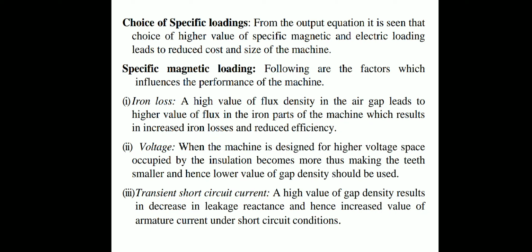Following are the factors which influence the performance of the machine. First point is iron loss. A high value of flux density in the air gap leads to a higher value of flux in the iron parts of the machine, which results in increased iron losses and reduced efficiency.